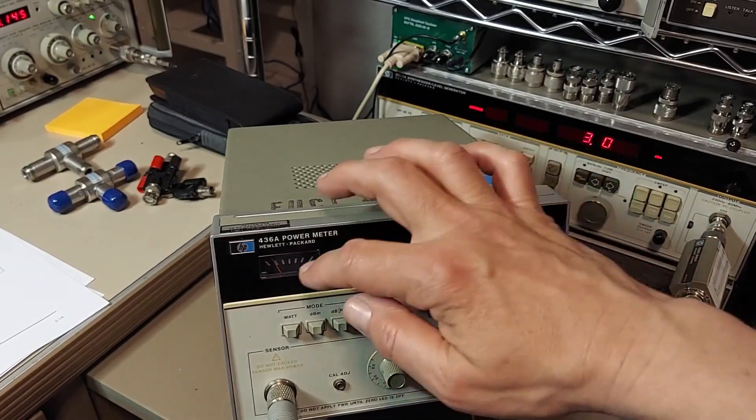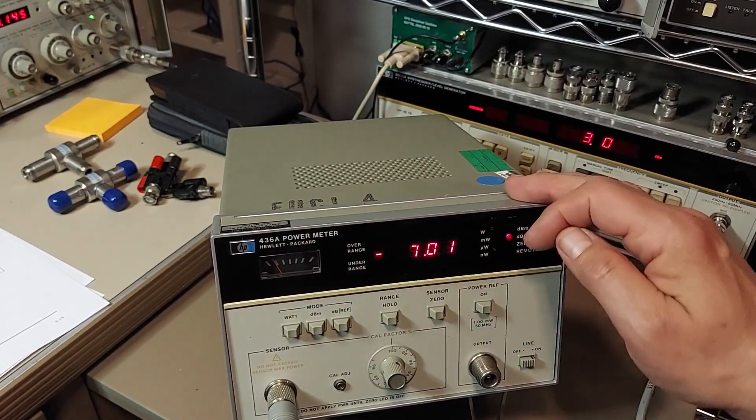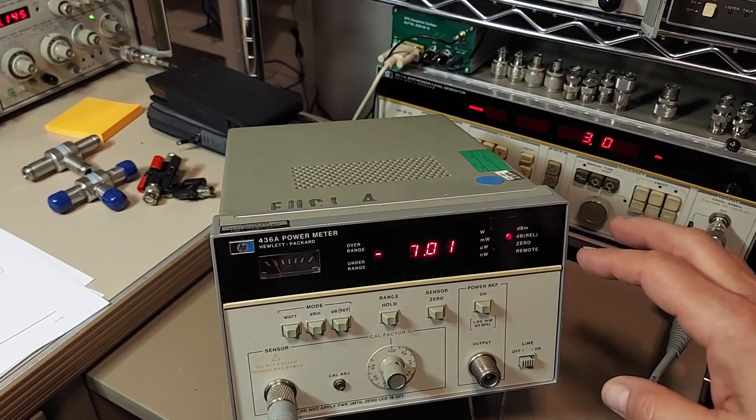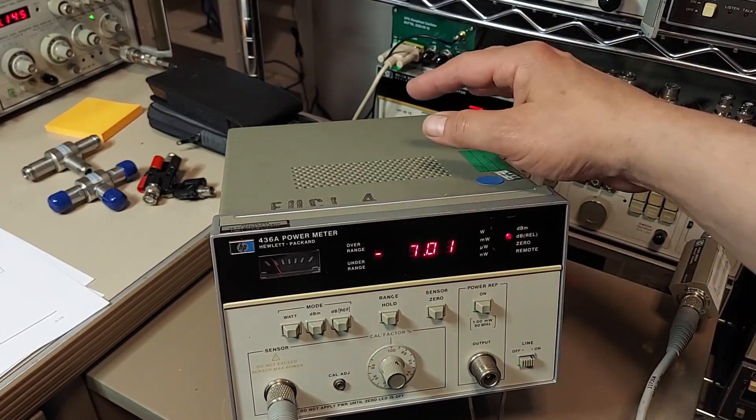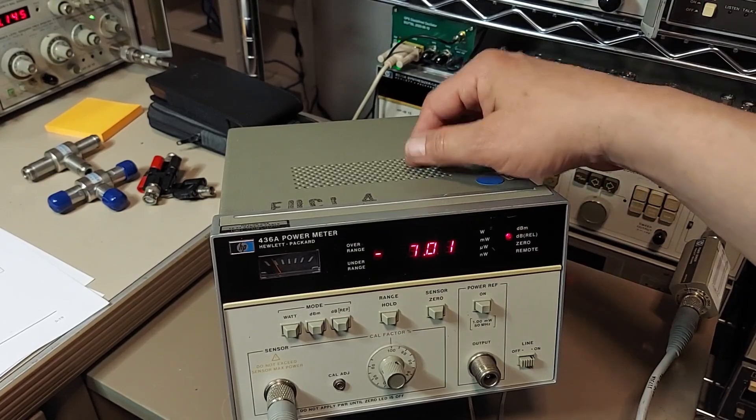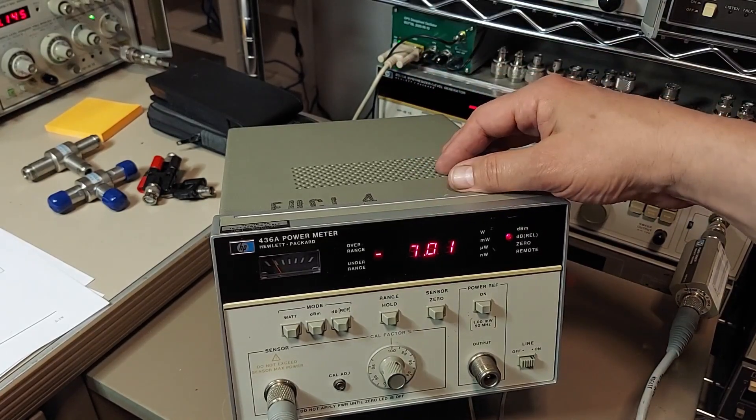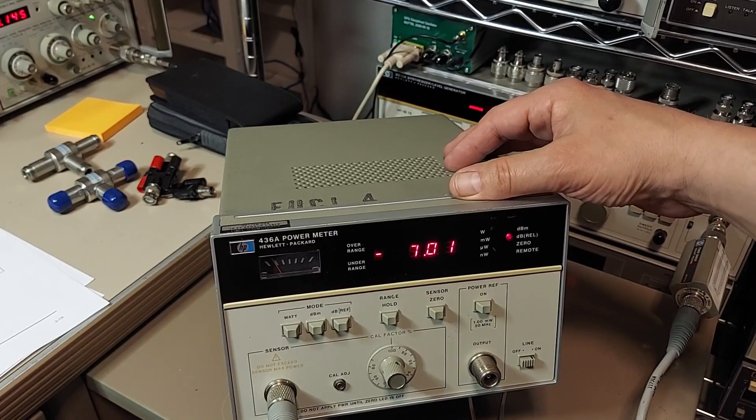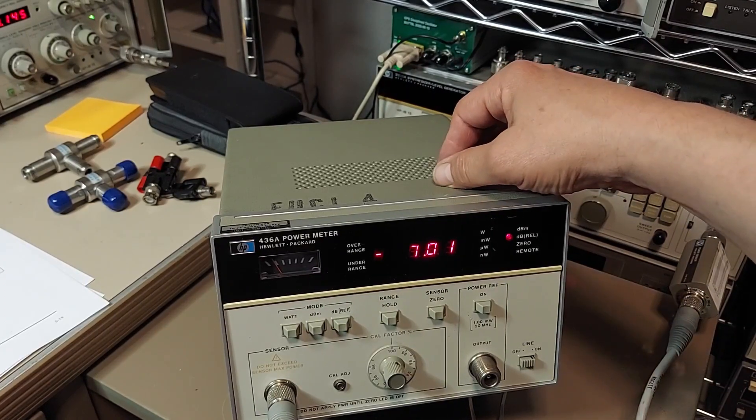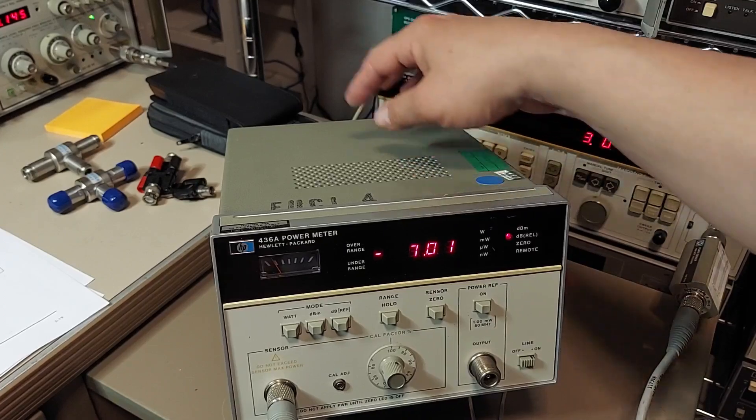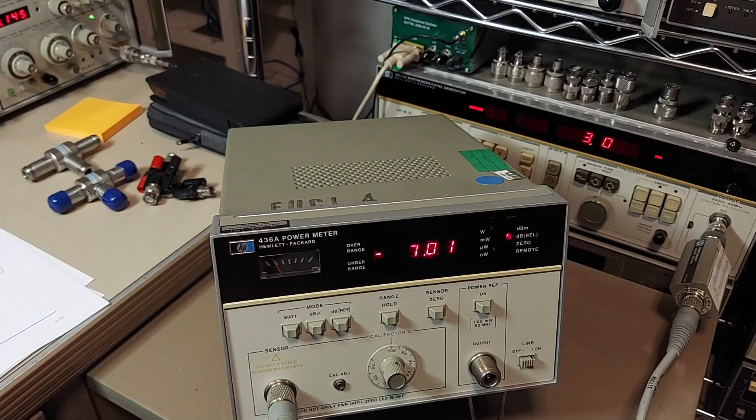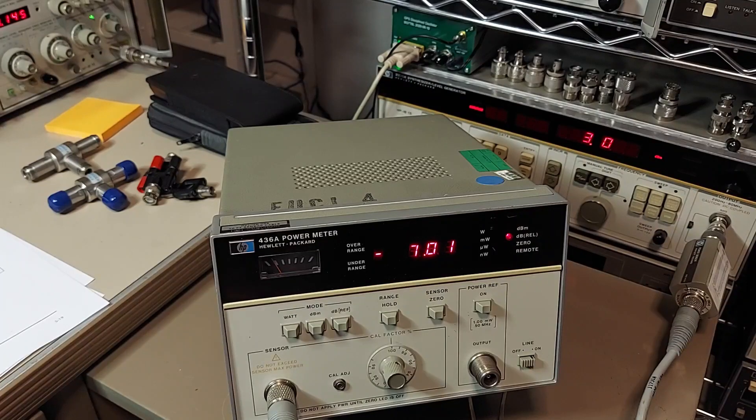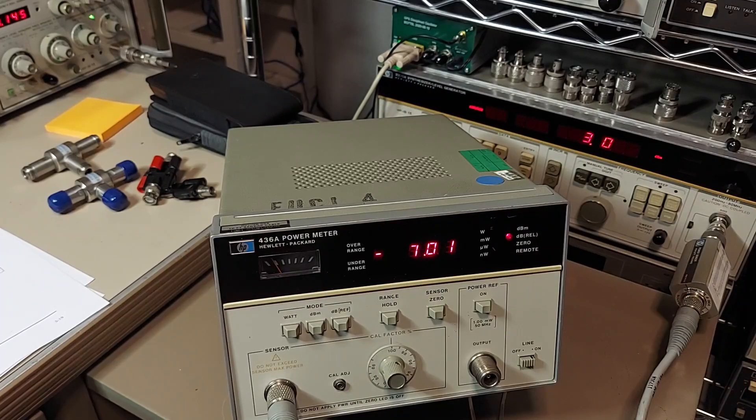Yeah, that's another useful feature. You can also hold whatever range the meter happens to be in at the time. You can't change the ranges; you can only do that over HPIB, but this particular meter doesn't have that feature installed. But I've got a couple of extra meters and I'm gonna rob the HPIB guts out of the others and install it in this so I can connect it to the rest of my instrument chain and actually control it via GPIB.